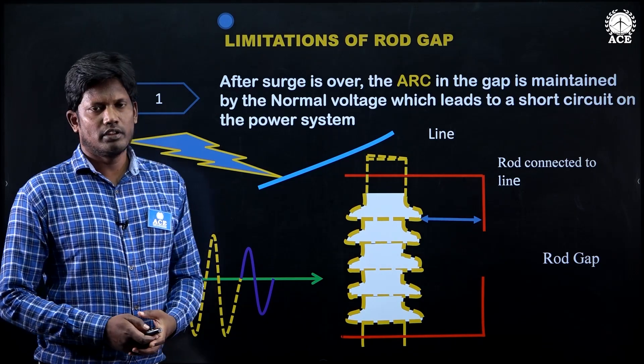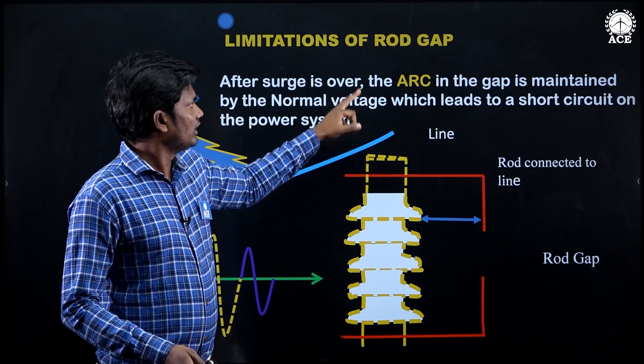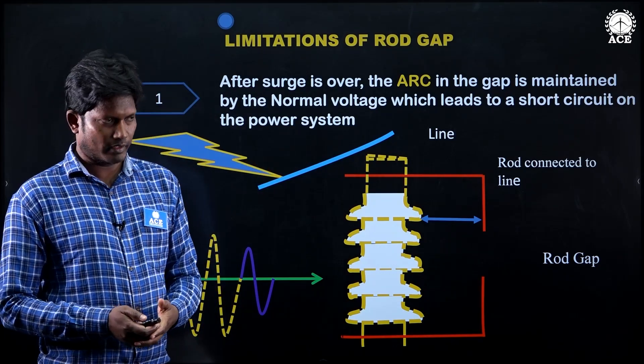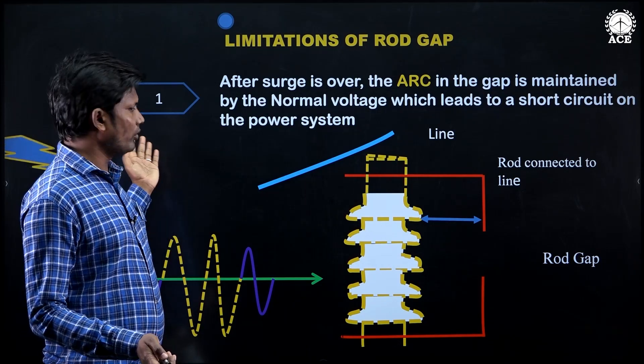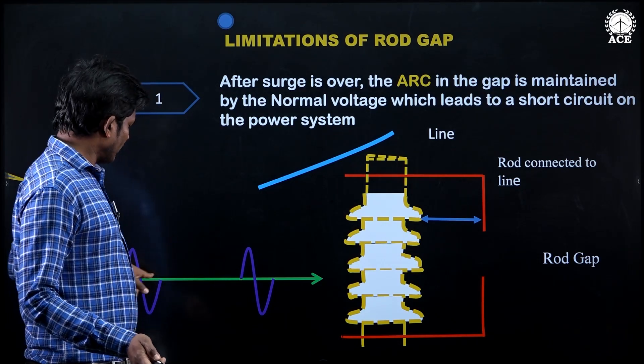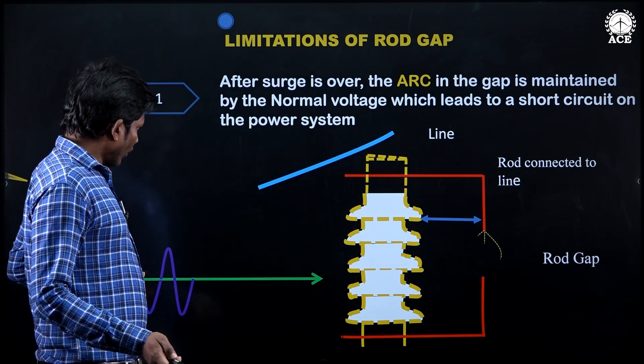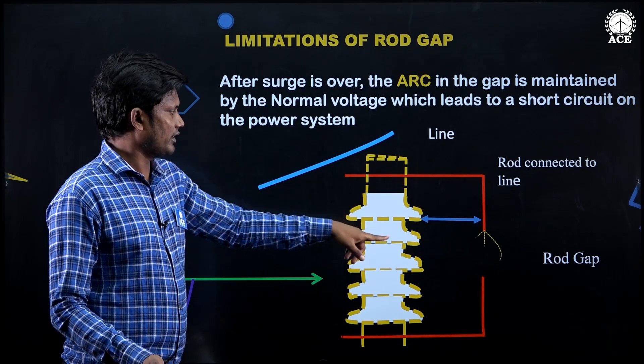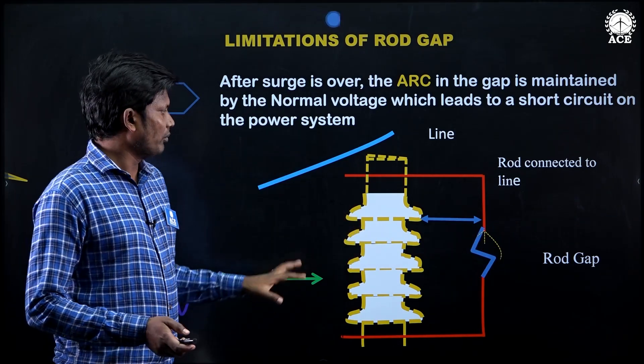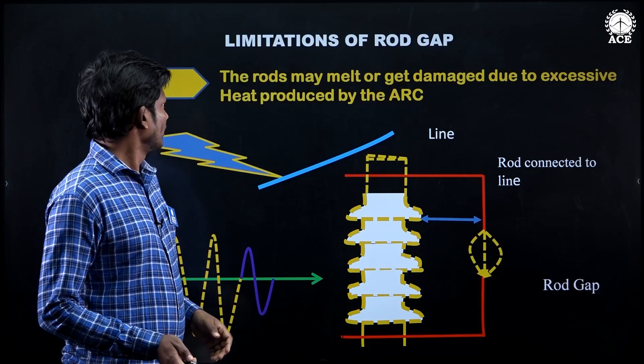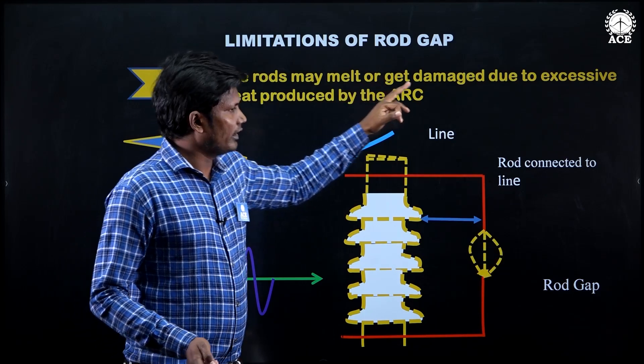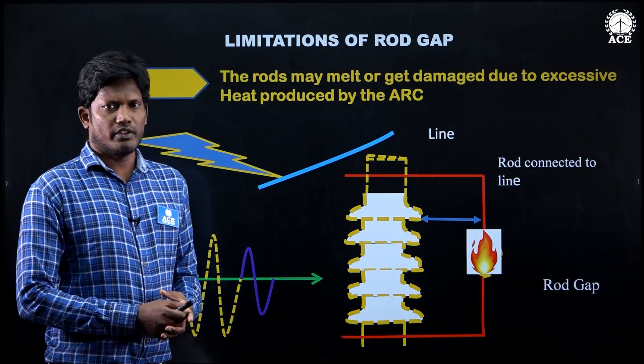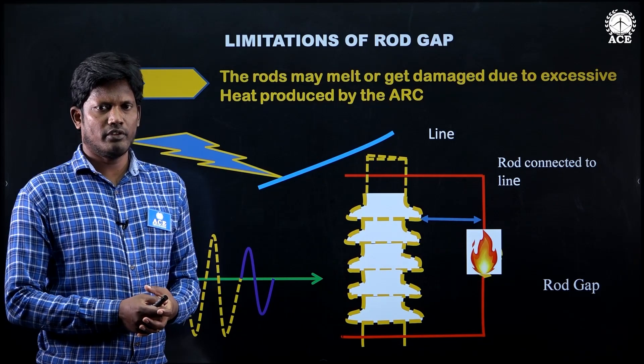Now the limitations of the rod gap. The first one is: after the surge is over, the arc in the gap is maintained by normal voltage, which leads to a short circuit on the power system. When the surge is over — meaning there is no lightning — the over voltage becomes normal voltage, and this normal voltage maintains the arc, causing a short circuit on the power system. The second limitation is the rod may get melted or damaged due to excessive heat produced by the rod gap. Due to these limitations, the rod gap arrestor is used only for backup protection of the main arrestor.